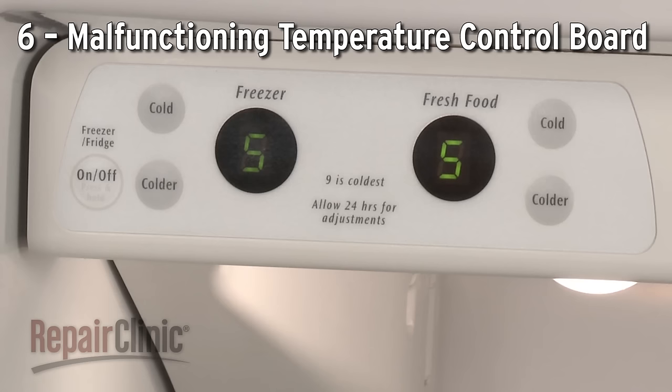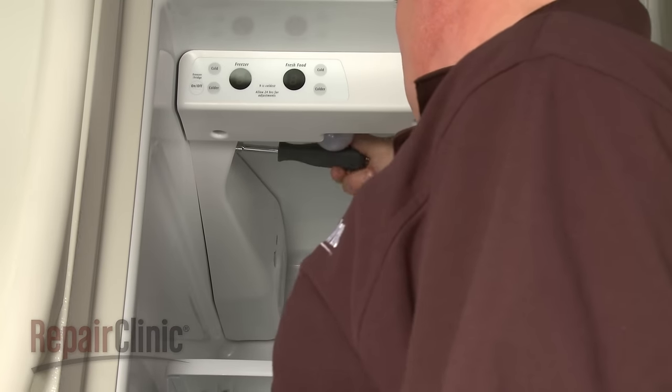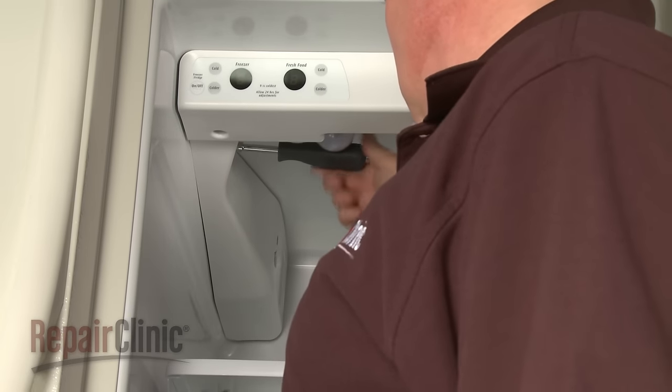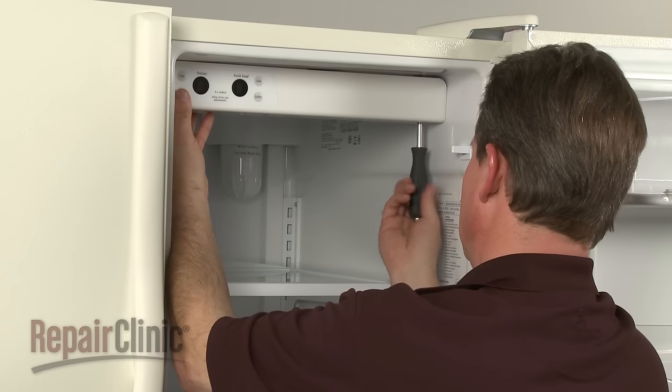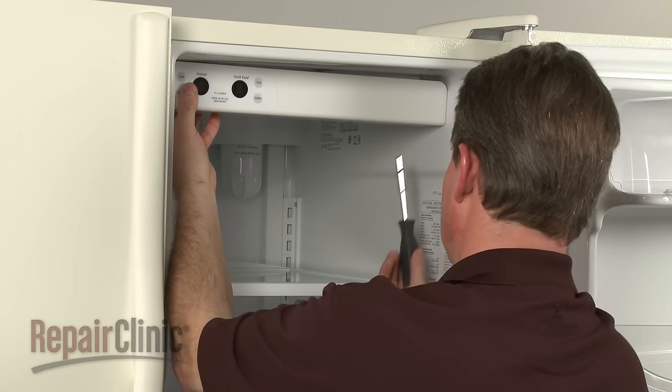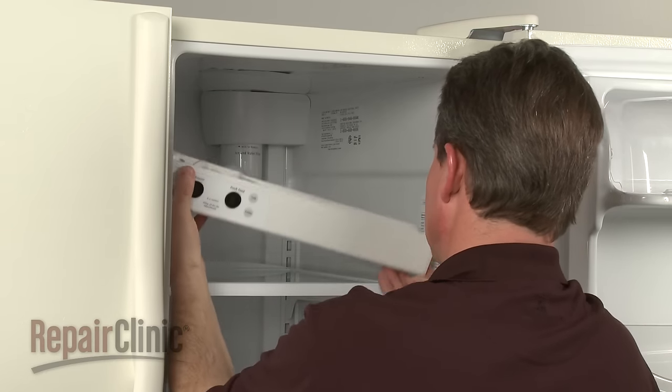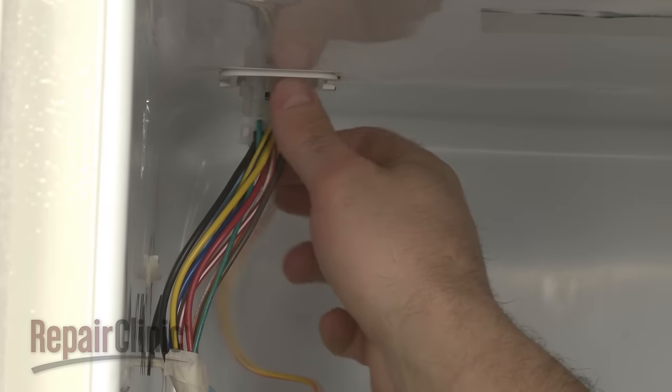The temperature control board allows voltage to be sent to the compressor and the fan motors. If the control board is malfunctioning, the cooling system won't cycle on. Since this is not a common problem, you should verify that the other components are working properly before replacing the board.